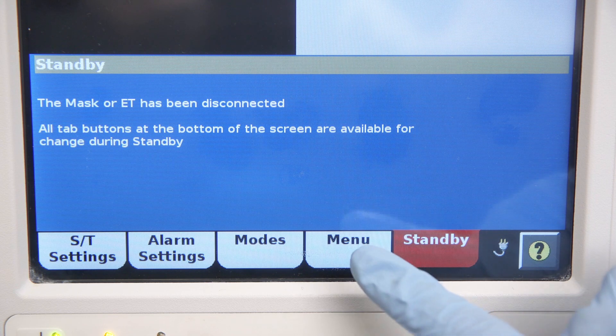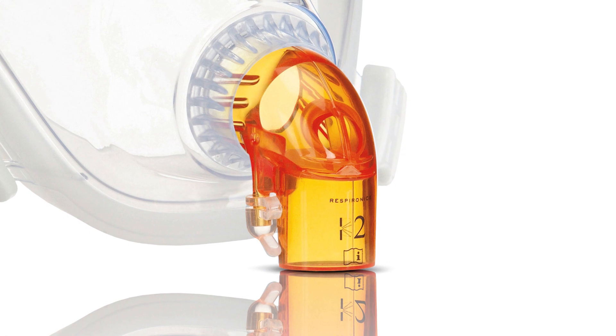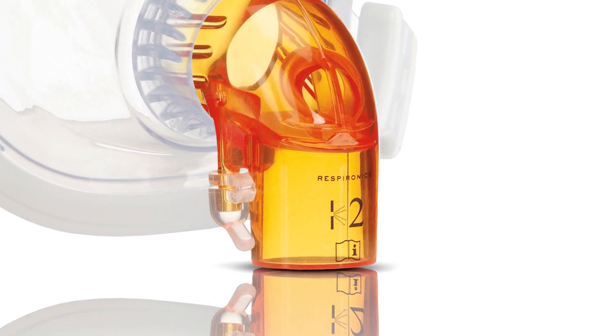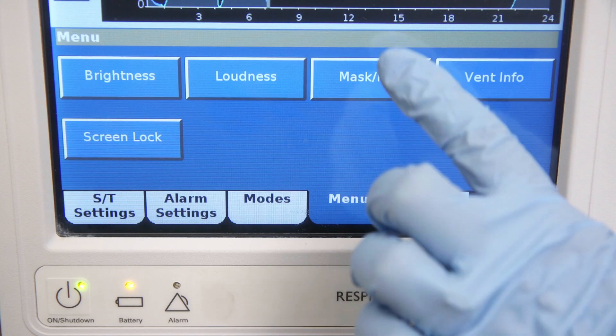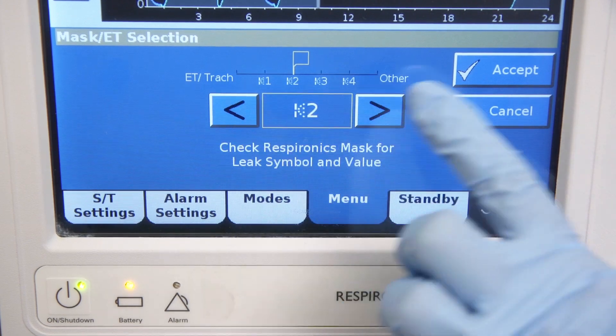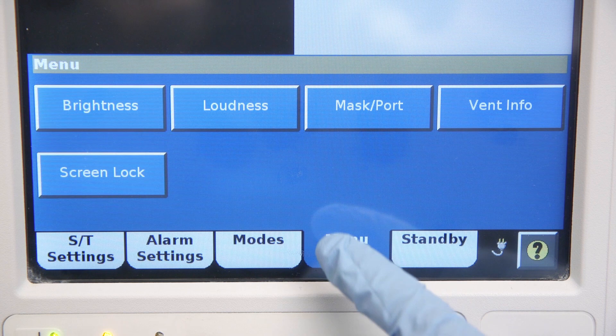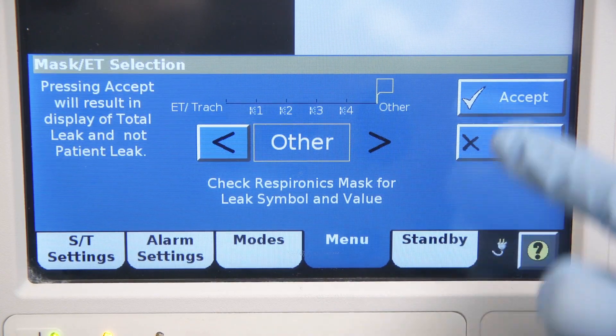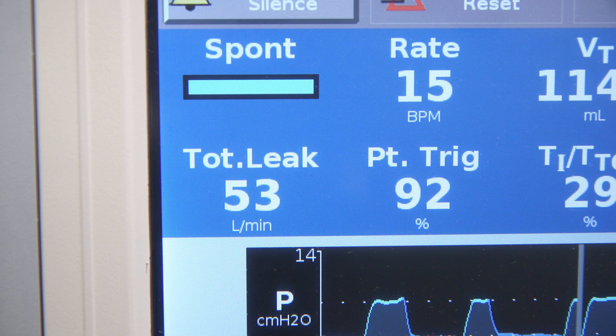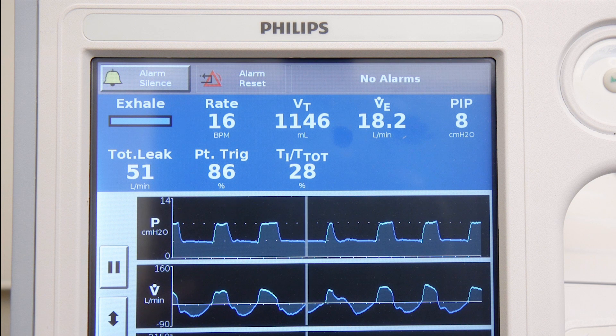To begin, touch the menu key on the Philips V60, then select mask/port. Locate the leak symbol on your mask. It may appear on the mask or on the elbow depending on the specific Philips mask. Using the arrow keys, select that setting on the V60. When using a non-Respironics mask, select the other setting in the mask/ET selection window. Please note that the patient leak value is now displayed as total leak. Selecting one of the Respironics mask symbols when using a non-Respironics mask may lead to erroneous patient leak readings and is not recommended.